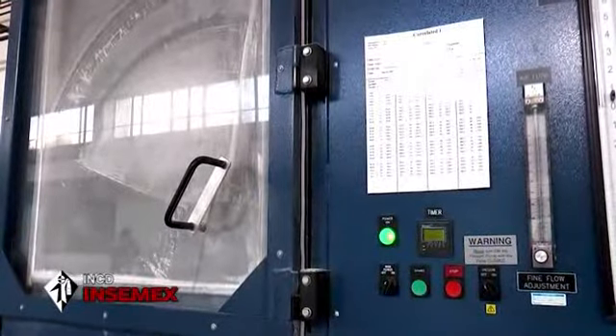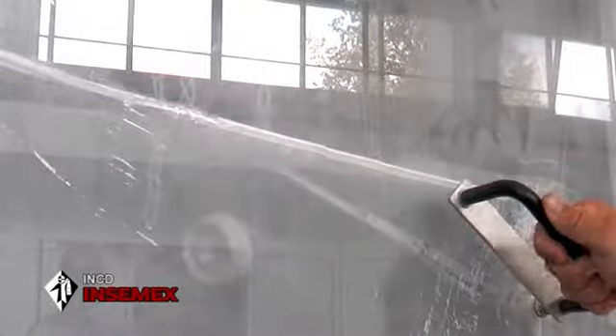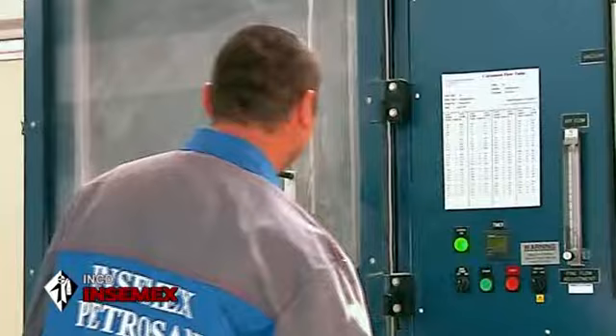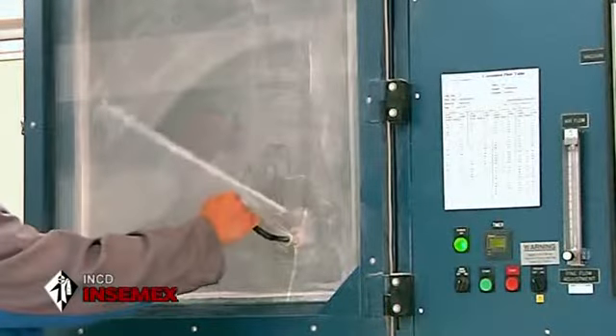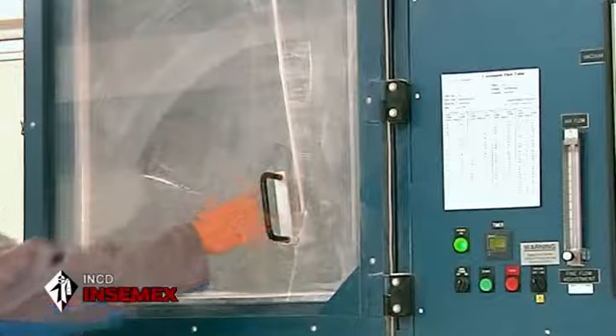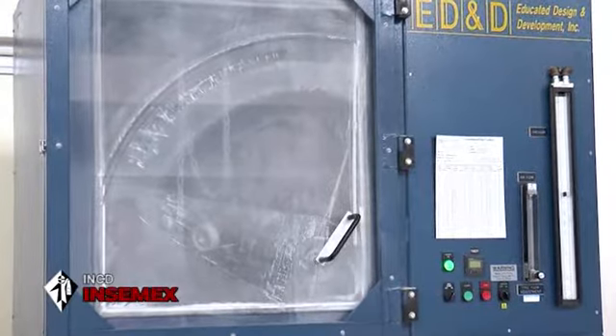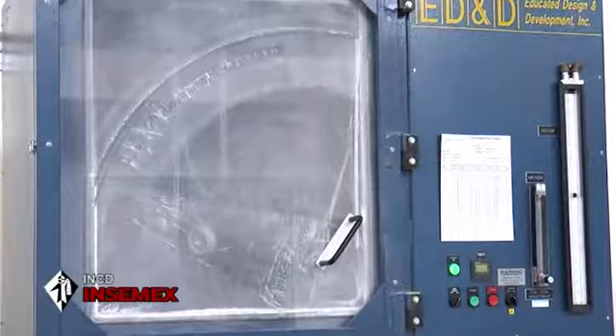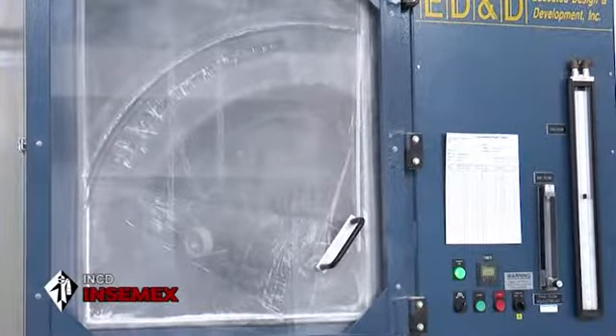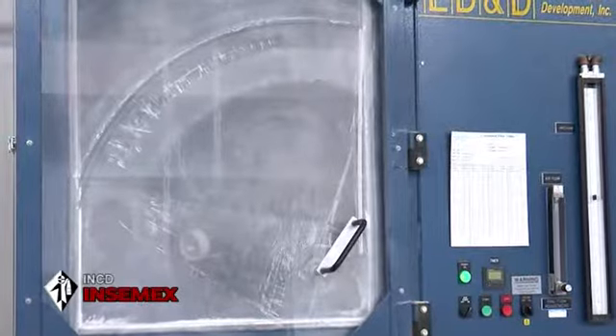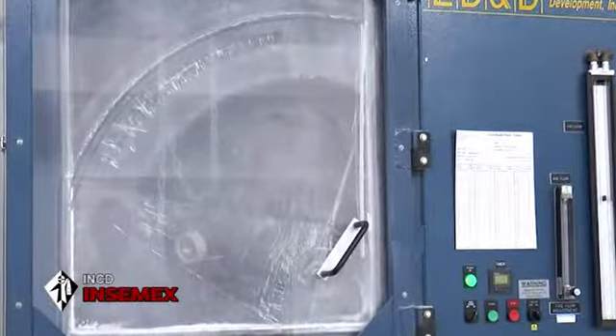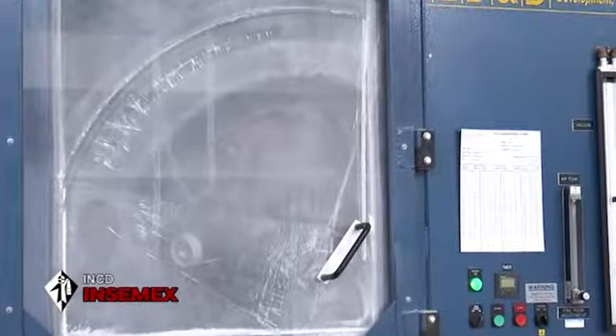Talc powder is used for performing the tests, 2 kg for 1 cubic meter of the test chamber, in compliance with the requirements of the European standard 60529, the chamber being fitted with a dust circulation pump for maintaining the talc powder in suspension. Depending on the type of enclosure of the electrical device, first or second category, equipment to be tested are located inside the testing chamber and the vacuum pump is used or not. For first category equipment, the test is performed at a depression of maximum 20 millibars. Second category enclosures shall not be subjected to such a depression, and the test will last for 8 hours. Any normally open exhaust hole shall remain open during the test.